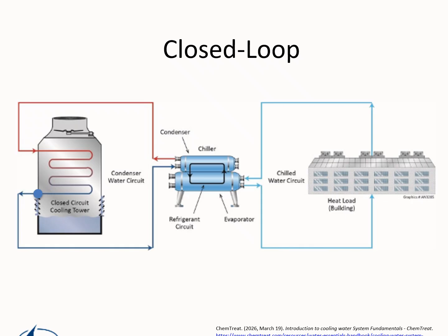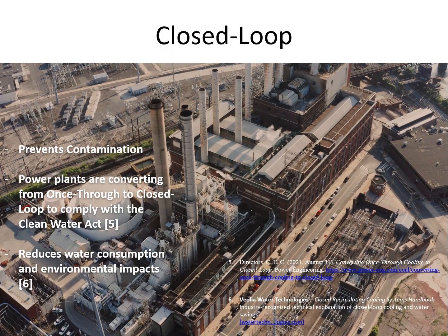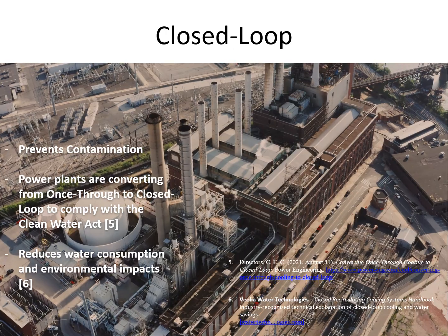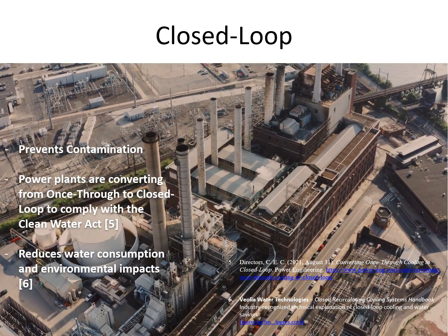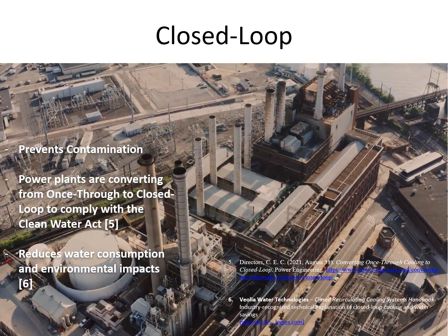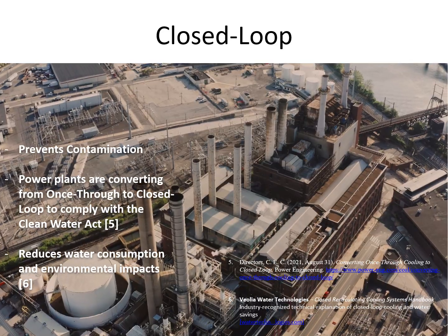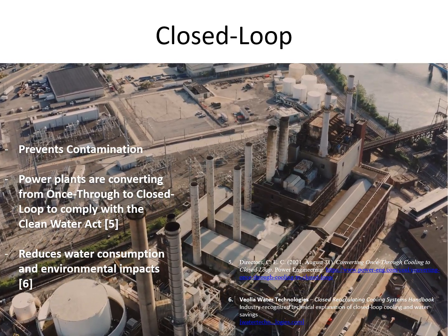Finally, we come to the closed-loop cooling system. In these systems, the processed fluid, usually water, circulates inside a sealed coil. It never touches the outside air. Heat is removed either through air alone or by spraying a small amount of water over the coil to boost heat transfer. Here's why closed-loop cooling is the most desirable option for water security. First, there is much less water consumption than open-loop systems. Because the cooling fluid is sealed, water losses are minimal.